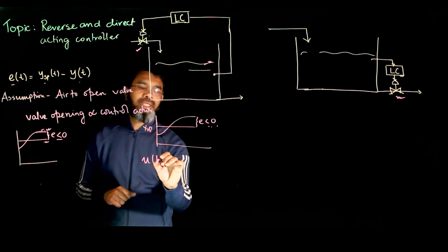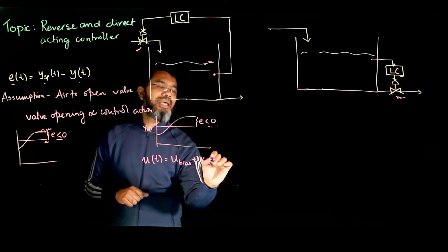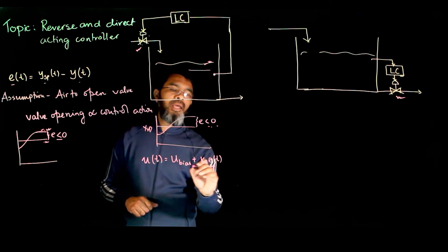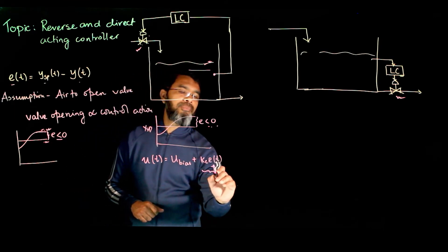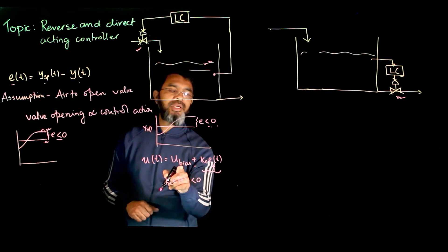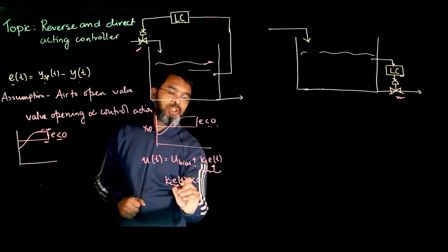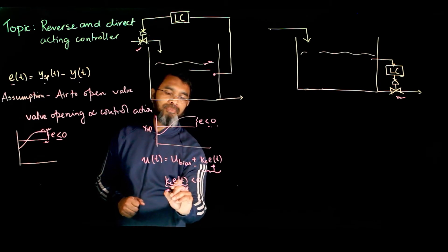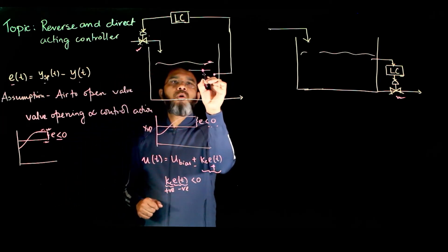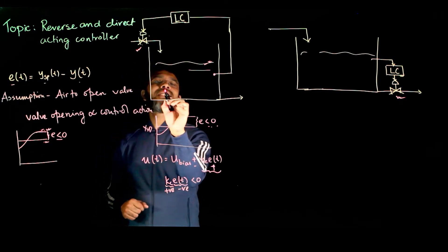Look at the equation for control action: U(t) equals U_bias plus KC times E(t). Here the error is negative, and if we need to reduce the control action, then the KC times E(t) term must be negative. Since error is negative, KC must be positive. This is what is called reverse acting — when the output exceeds the set point, you reduce the control action. So reverse acting means KC greater than zero.